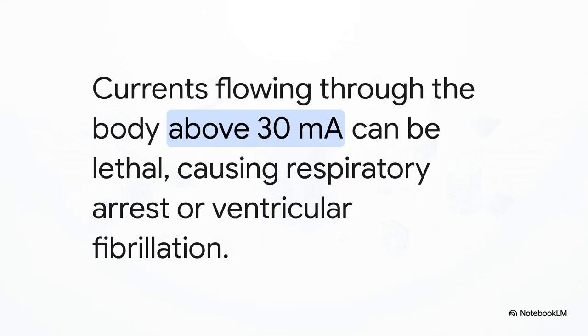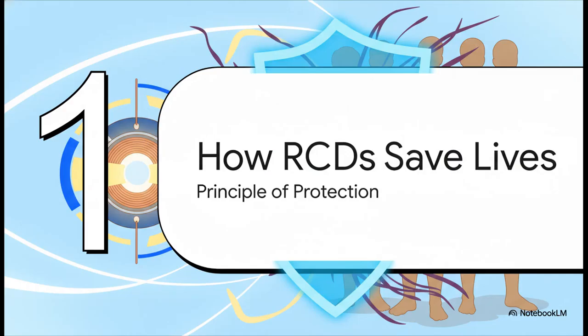And the danger isn't just about fire. The international standard IEC 60479-1, which spells out exactly what current does to the human body, is crystal clear. The moment a current flowing through you gets above 30 milliamps, it can stop you from breathing and, most critically, cause ventricular fibrillation. That right there, that's the lethal line in the sand that shapes our entire approach to keeping people safe. So how do we actually defend ourselves against these invisible dangers? Well, the answer is in this brilliantly simple principle of physics, all wrapped up in the residual current device.